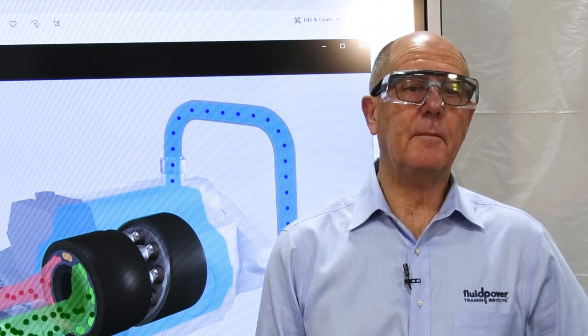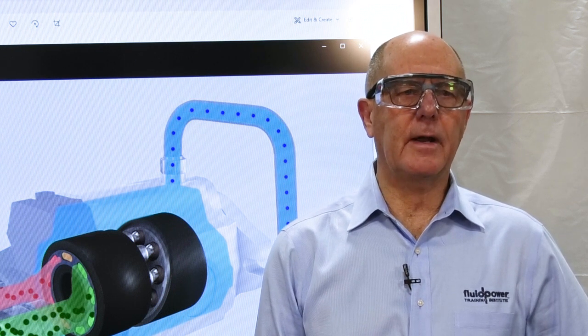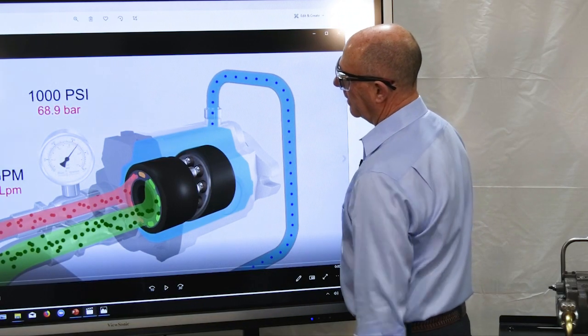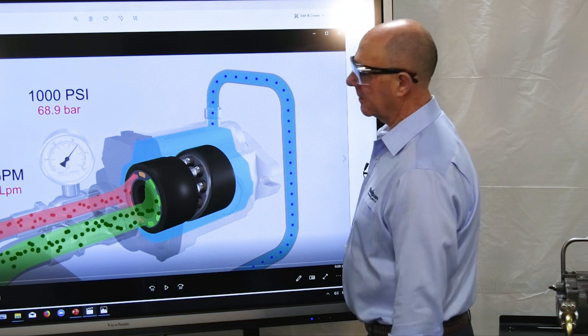For a period of 10 years, I disassembled and inspected hundreds of hydraulic components to determine why they had failed. To no surprise, I found that contamination was the root cause of over 95% of hydraulic component failures. When I studied wear in external drain pumps and motors, I found that wear paths that contamination created did not lead the oil to the case, but rather led the oil to flow from the pump's discharge chamber back to the pump's inlet chamber. This is an exploded view of an axial piston pump.